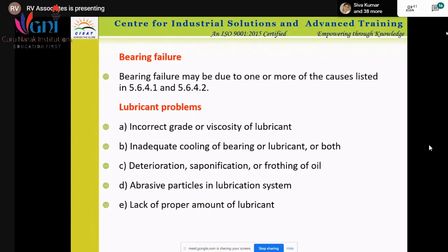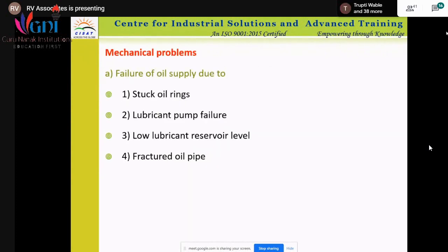Then there is bearing failure, maybe because of oil, because of the load, or maybe deterioration. These are all mechanical problems. Failure of oil supply: why does it happen? It may be that a pump is not working, or the pipe through which the oil is flowing has been blocked. So anything is possible. That's why, as told for the transformer, any failure of the support system will lead to a fault.